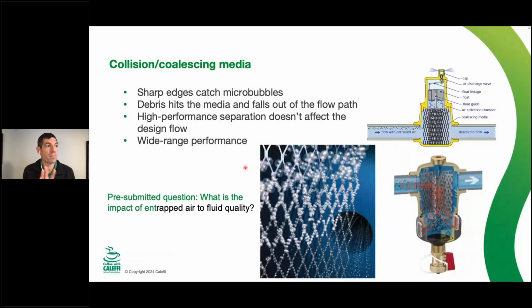So what's the difference between an air vent and an air separator? It's the bottom half of this device here. This is our coalescing media, which is a very fancy way to say to gather. Coalescing is to gather these air bubbles so they don't just blast straight through the device. They catch on these little sharp knife edges of this polymer media, build into bigger bubbles, and then go up to the top. So an air separator is grabbing and separating the air out of the system. An air vent really only vents air that's accumulated at the top.